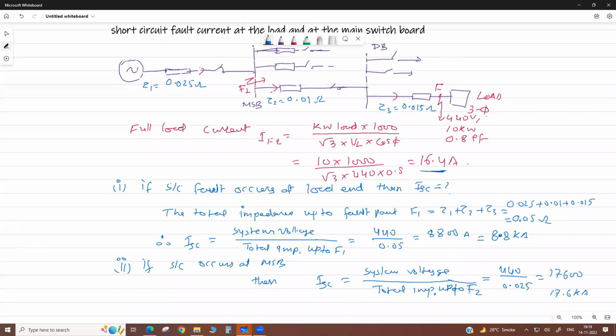So as we come upstream, meaning near to the source, the fault level is high. As we go downstream, the fault level is reduced because the series impedance is increased, okay.